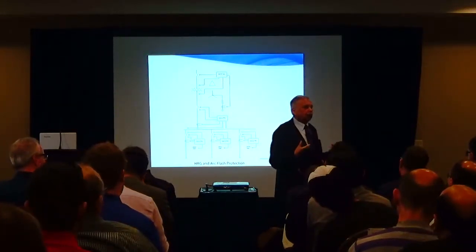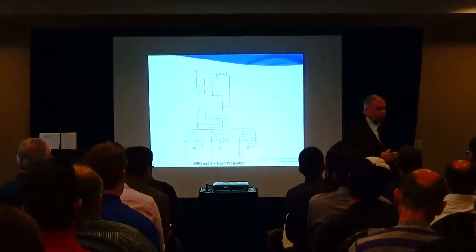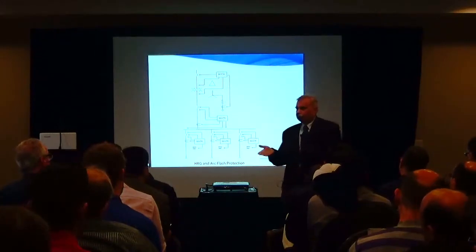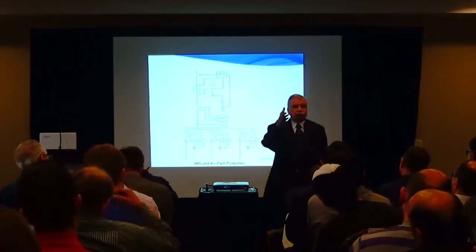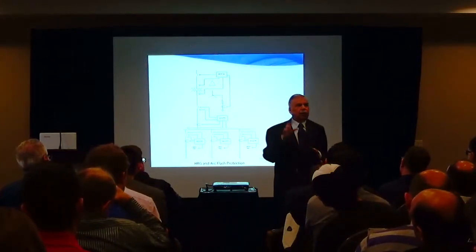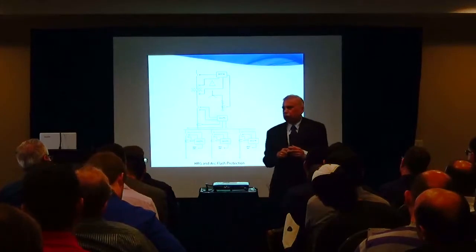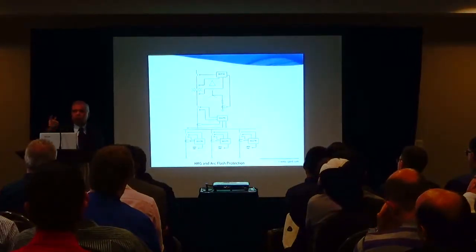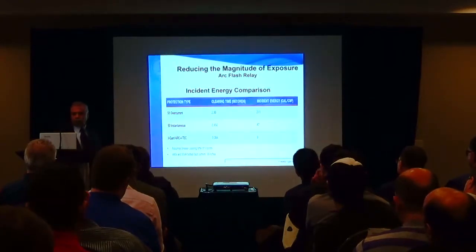Now in Canada and US, we have a need for a visible break. When you apply vacuum interrupters, there is no visible break. You can't see through the vacuum bottle. So you need a disconnect with a vacuum interrupter. Okay, so a manual disconnect, just for a visible break. So you interlock. So when the vacuum breaker is open, you can pull the switch off load, and you have a visible break. Now it complies with the code. And you have a viewing window to see that visible break. So a visible break with a vacuum interrupter is all they need. So once you do that, you have this. So this is an effective approach to addressing these high exposure situations where you can keep the calories low.